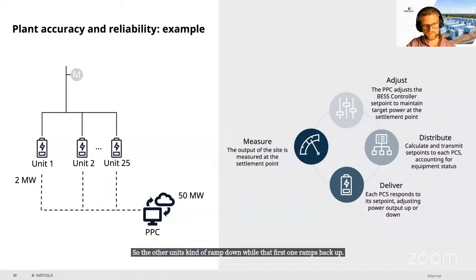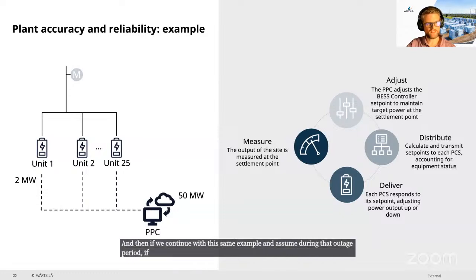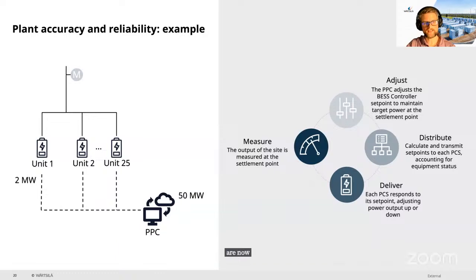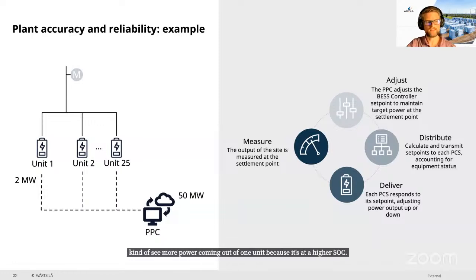And then if we continue with this same example and assume during that outage period, those batteries are now 10% higher in SOC than the rest of the other 24 units, this is where an SOC balancing type power allocation, like the one Sunitha was talking about, would come in and allocate a larger portion of that discharge demand to that unit 1 to drive its SOC back down to the SOC of the other units. So you kind of see more power coming out of one unit because it's at a higher SOC. And then that will drive the SOCs back to that balanced level.